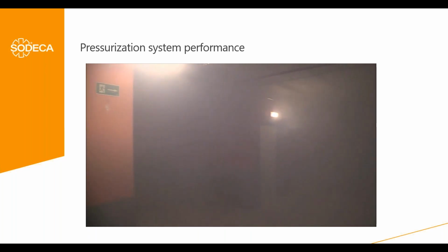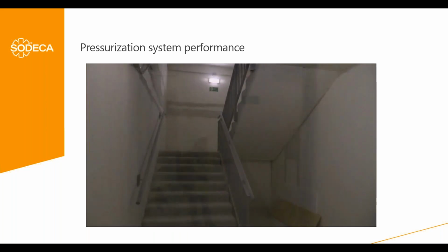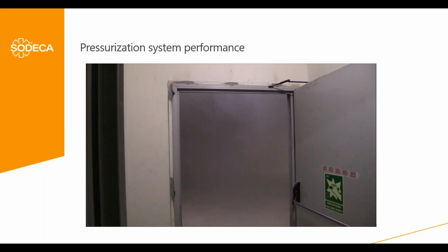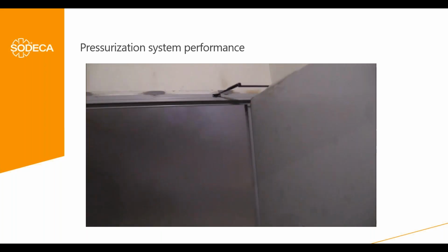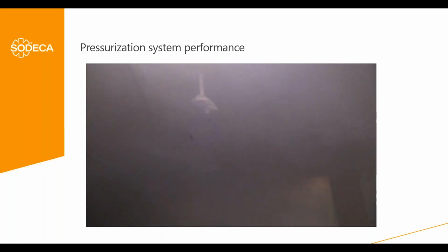And so we went to the staircase that was pressurized, and even with the door open, you see how when we went in, there's the lobby and the staircase was pressurized, so absolutely empty of smoke. Outside we have a lot of smoke because the machine that generated the smoke was very close to this exit, but inside the staircase was completely free of smoke.